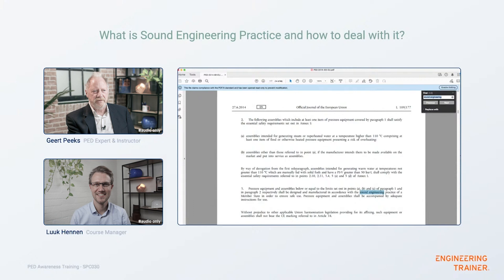Regarding documentation and CE stamping: in Article 4 paragraph three, where sound engineering practice equipment is defined, you need a manual in order to use this kind of equipment — similar to how a coffee machine comes with an operating manual. That is the only thing the Pressure Equipment Directive requires you to provide. CE marking is excluded — in fact, if you put this type of equipment into the market, it is forbidden to stamp it with a CE mark.